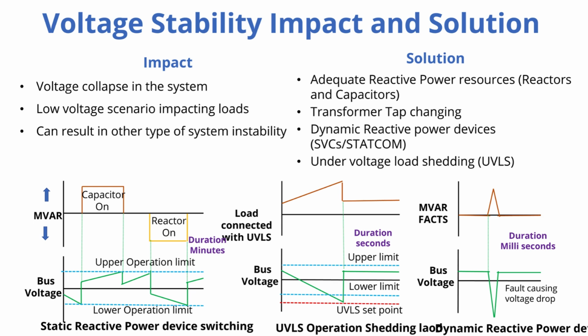UVLS again. Yeah. Sounds like the voltage equivalent of UFLS for frequency. Exactly. It's an emergency protection. If voltage drops below a critical level, UVLS automatically disconnects blocks of load, to reduce reactive power demand and hopefully stop the voltage from falling further. Precisely. Sacrifice some load to save the wider system. Yeah. The graphs also show how different reactive devices impact the voltage-load relationship, and that voltage collapse typically happens over seconds to minutes, slower than transient, faster than some frequency issues.